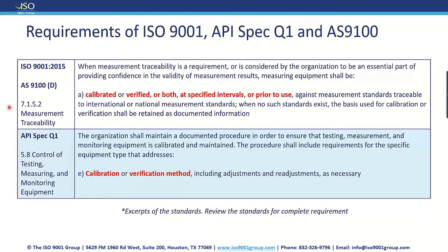It says, when measurement traceability is a requirement or is considered by the organization to be an essential part of providing confidence in the validity of measurement results, measuring equipment shall be, and of course there's more, and I just took an excerpt from the section that's applicable to our topic today. It says, A, calibrated, or, this is very key, and when you're reading standards, you have to really pay attention to the language. It says or, which means option, right? Calibrated or verified. Another or here, or both, or calibrated or verified, or you can do them both, calibrate and verify. All right, next thing, part of that clause, it says that it should be done at specified intervals.